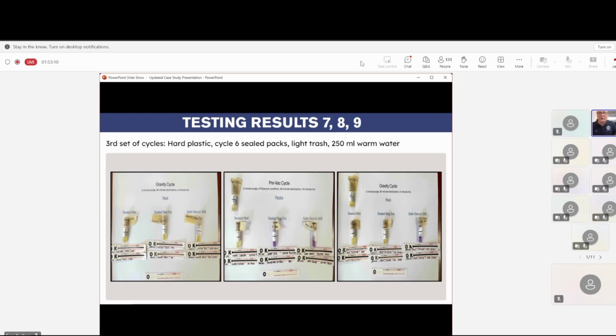So I ran one more on number 9, the last of the 40-minute cycles, and you'll see we got failures on both the gravity runs. This is the loose version of the pack I showed you before — it wasn't taped down, just hinged and shut. The BioPro 300 got it, but look at your steam strips — it's showing we got through this just fine.